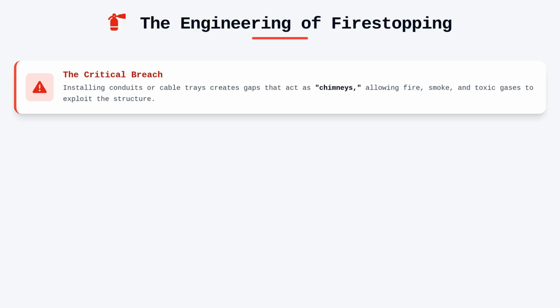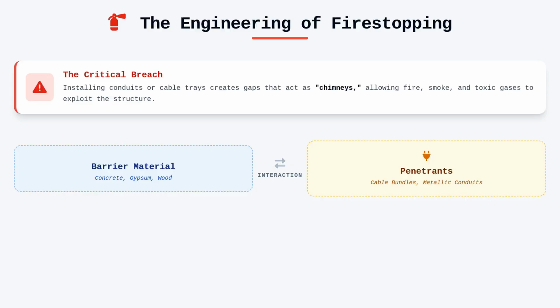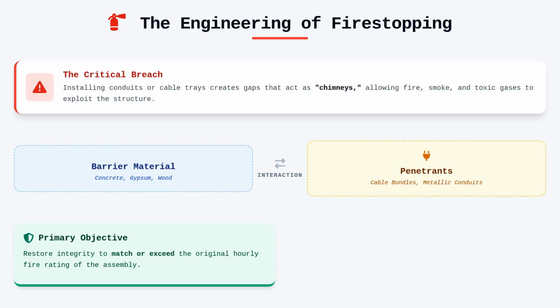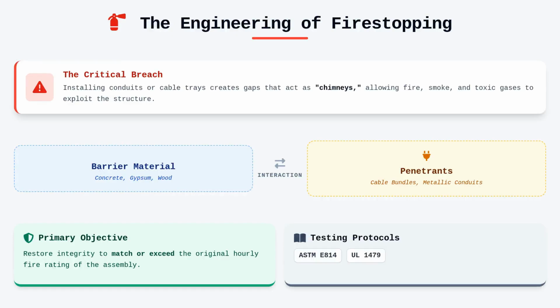To achieve this, practitioners must understand the interaction between the barrier material, which could be concrete, gypsum, or wood, and the penetrant, such as cable bundles or metallic conduits. We rely on standardized testing protocols, specifically ASTM E814 and UL 1479, to define the performance criteria. These standards provide a consistent framework for measuring how well a material holds against the hazards of a combustion event. Without this rigorous oversight, a pathway serves as a chimney, accelerating the spread of a fire throughout a building.